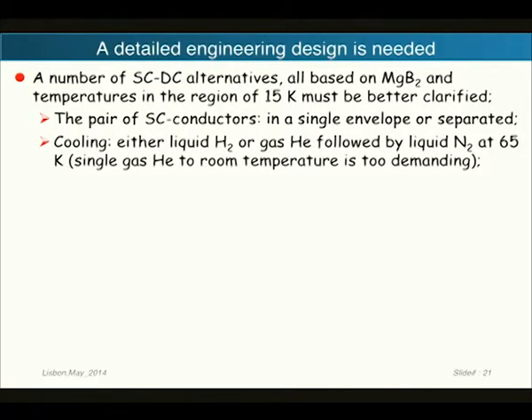Cooling can be either liquid hydrogen, as you'll see, or helium gas followed by liquid nitrogen at 65 Kelvin. Single gas helium to room temperature is too demanding.